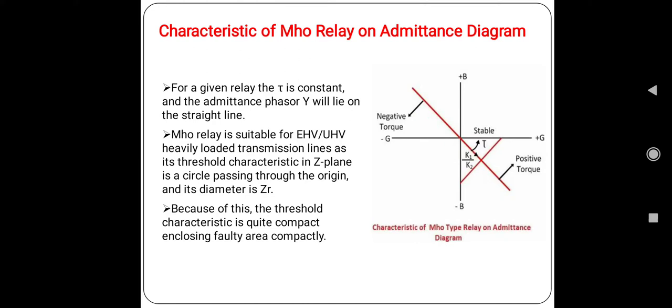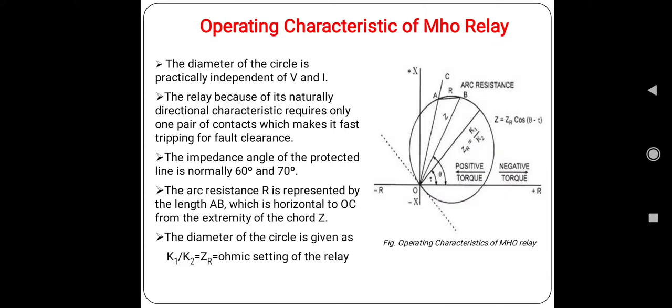Mho relay is suitable for long extra high voltage and ultra high voltage heavily loaded transmission lines. Its threshold characteristic in the Z plane is a circle passing through the origin, and the diameter is ZR. This is the ohmic setting of the relay.